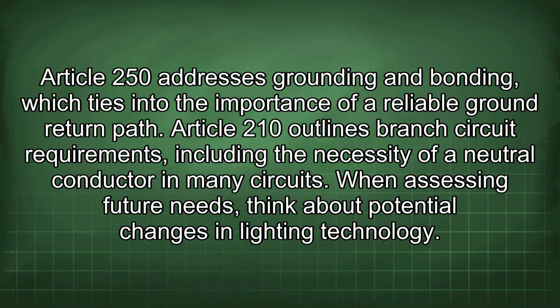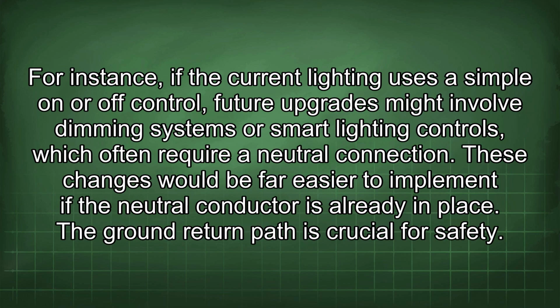When assessing future needs, think about potential changes in lighting technology. For instance, if the current lighting uses a simple on or off control, future upgrades might involve dimming systems or smart lighting controls, which often require a neutral connection. These changes would be far easier to implement if the neutral conductor is already in place.